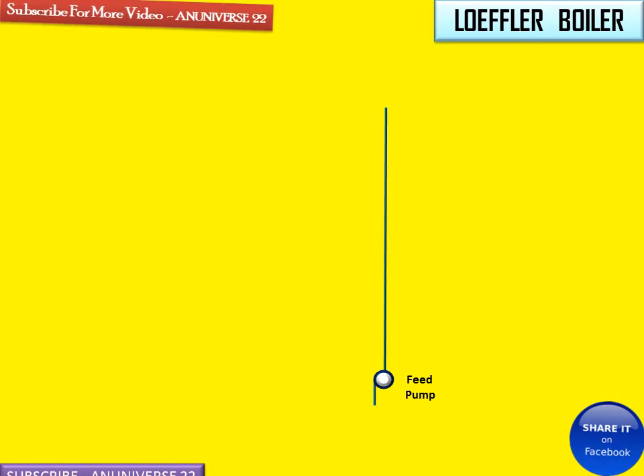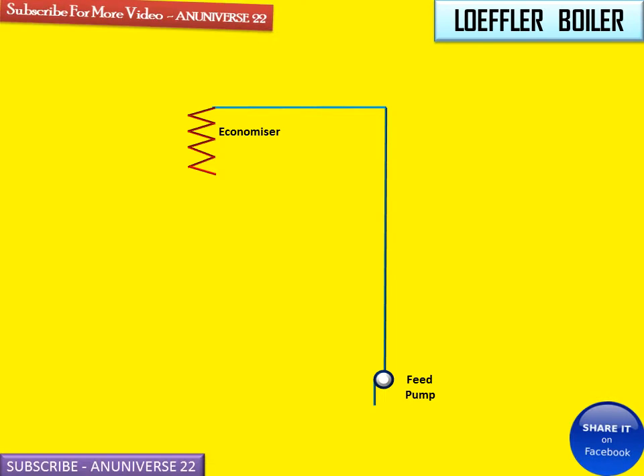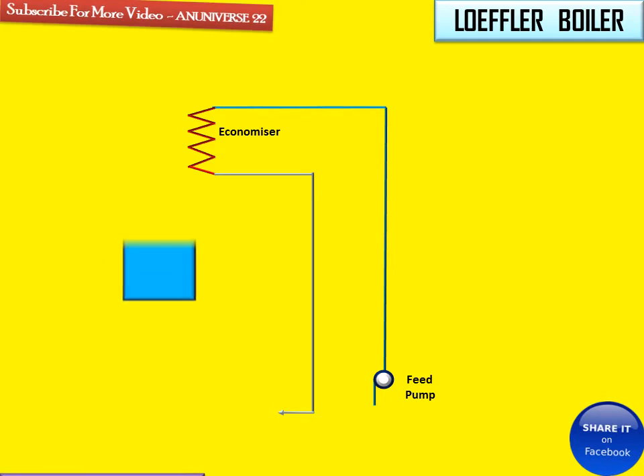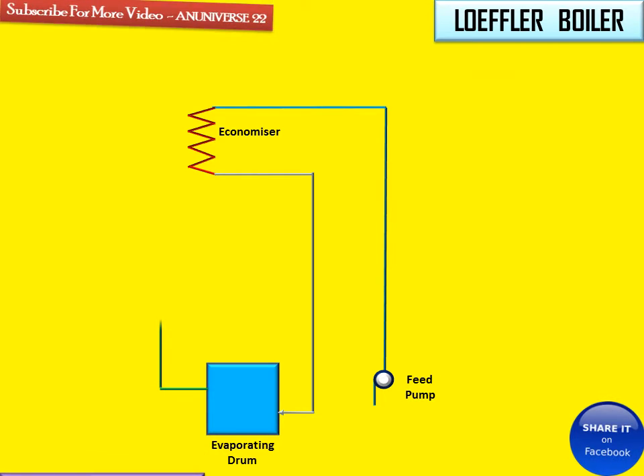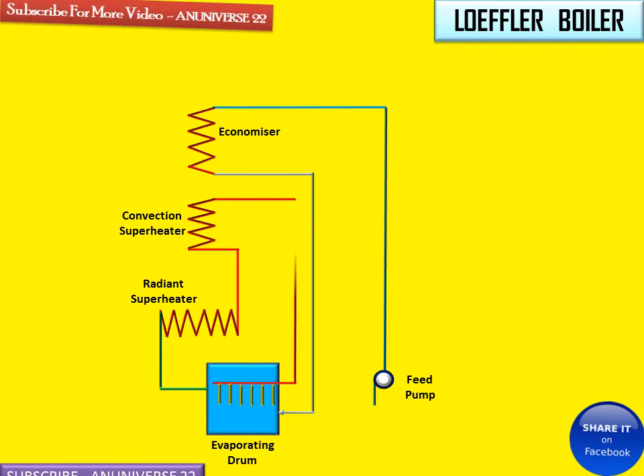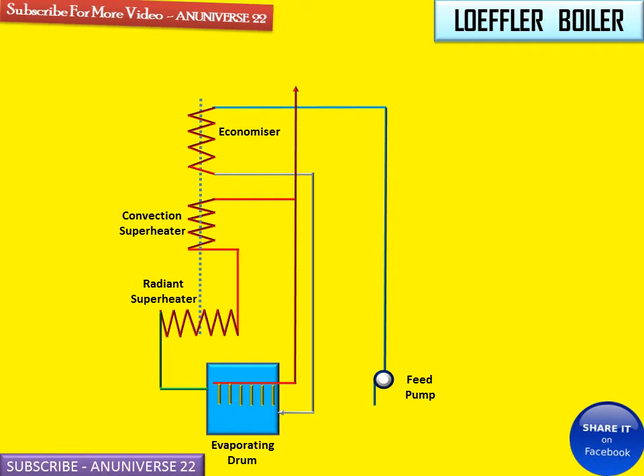Now we will discuss the main components of the Loeffler boiler: the feed pump and the economizer. Feed water is circulated through the economizer tubes by the feed pump, and hot flue gases pass over the economizer tubes to preheat the feed water. From the economizer it is connected to the evaporating drum, and there is also the radiant superheater and convection superheater. The dotted line shows the path of flue gases from the combustion chamber to the atmosphere.